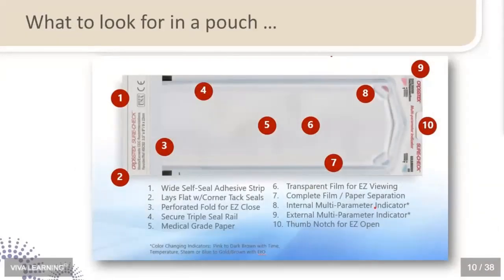I'm just going to go through not all 10 of the features, but things that when you're looking at the pouch, you know, don't just say, yes, it's got a flap and it's sealed on 3 sides. You want to look at the width of the adhesive. The wider the width, the more effective your tamper-resistant seal is going to be, because that adhesive strip has to actually be seated specifically 50% on the laminate and 50% on the paper, because that's what's going to create that complete seal. So the wider the laminate, the better the seal. It's also helpful to look for a perforation where that tab is joined to the paper, because that perforation is going to help to guide that tab so that it seats appropriately at the best spot.